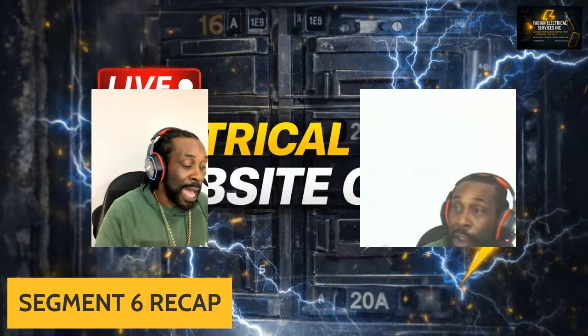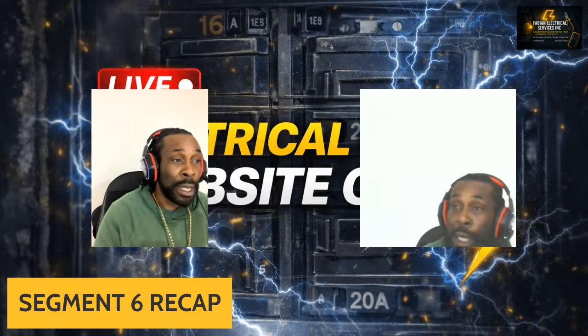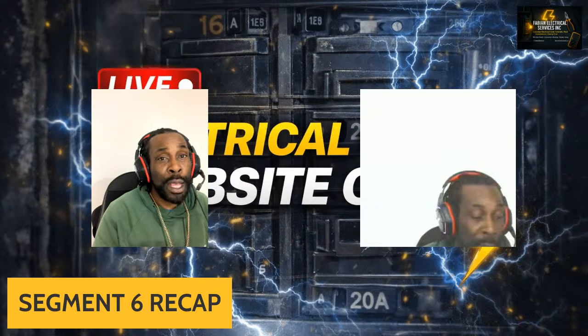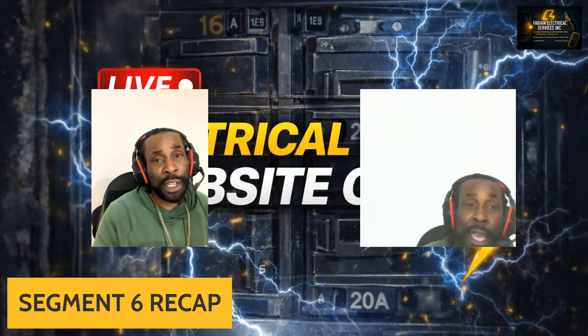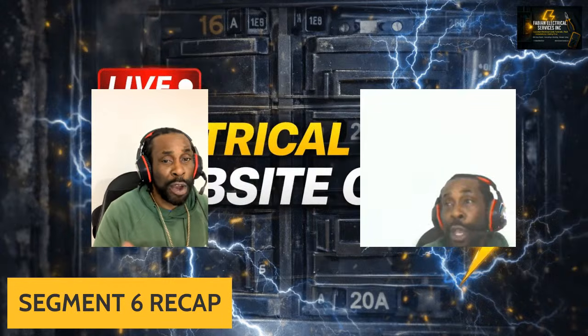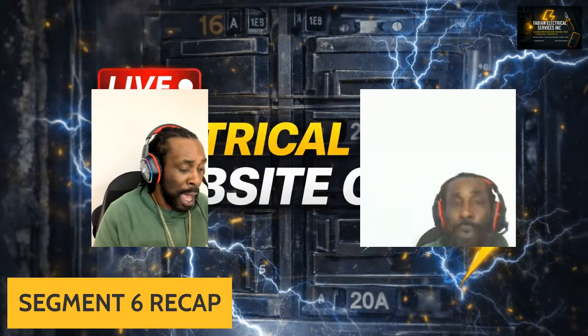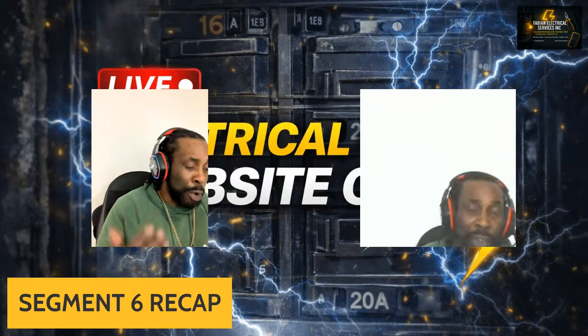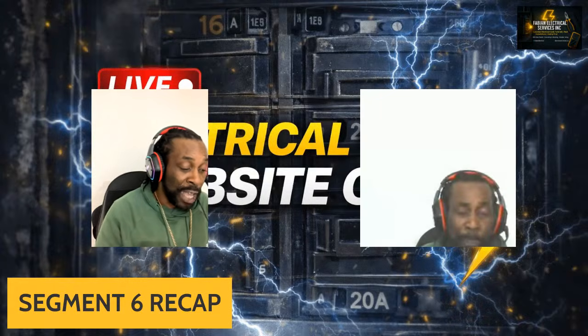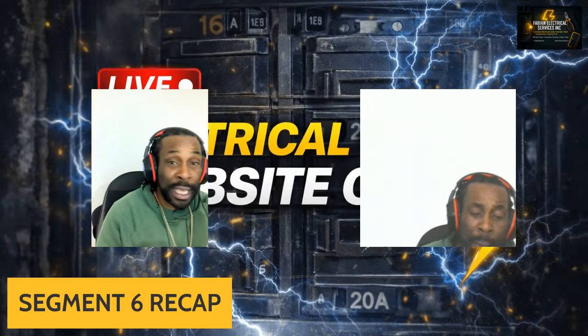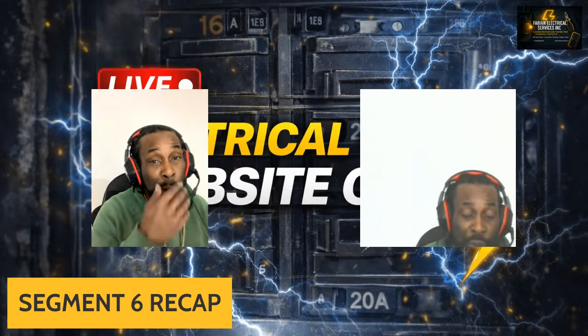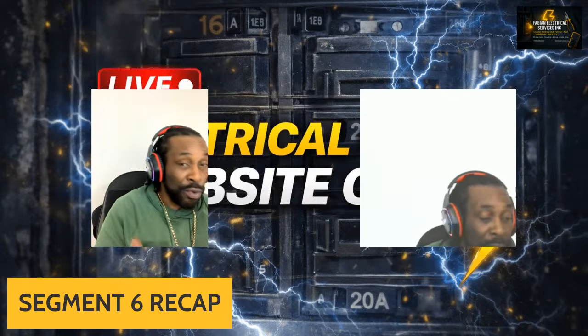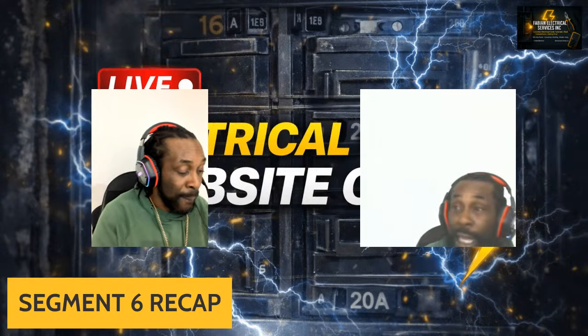You can find that in the actual code book, 8-104, and then also 14-101 is part of the actual rule. So again, most people get this wrong. They size based on devices and not the wire. This is part of what I would have covered through the live stream tonight.